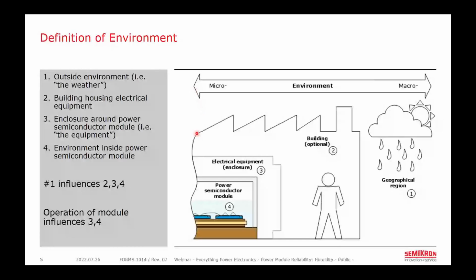So what we have here is a power semiconductor module, exaggerated in scale, which is mounted inside a piece of electrical equipment, perhaps a motor drive or solar inverter. Depending on the application, that electrical equipment enclosure might be rated for outdoor use, so we show this building here as optional. We usually speak about one environment with a given set of temperature, moisture, wind, pollution, etc. But for the purposes of this discussion, it's really important to differentiate between the larger macro environment outside, shown here as one, and the different micro environments that can occur around and inside a power semiconductor module.